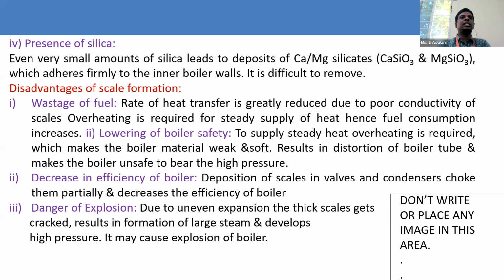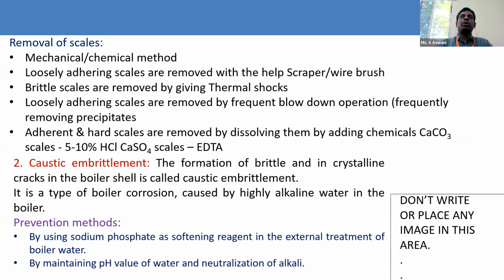So these are the disadvantages of scale formation. How are we going to remove the scales? There are mechanical and chemical methods for removal of scales, and we are going to follow those. Loosely adhering scales are removed with the help of a scraper and wire brush. These are the simple techniques to remove hard scales. And brittle scales are removed by giving thermal shocks.